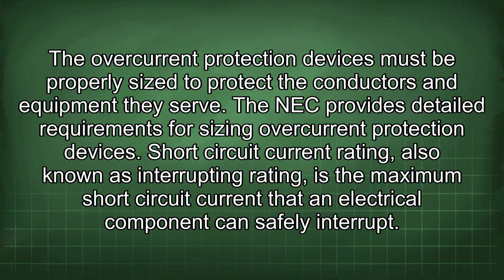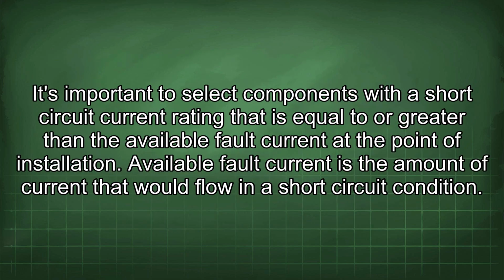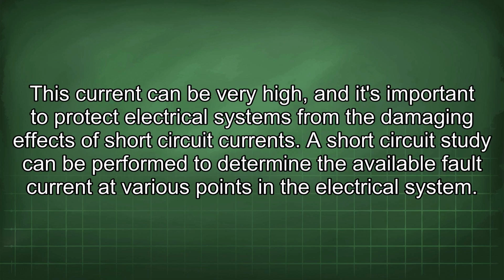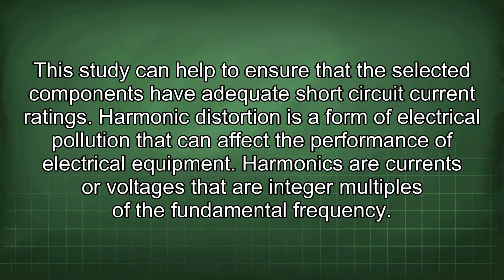Short circuit current rating, also known as interrupting rating, is the maximum short circuit current that an electrical component can safely interrupt. It's important to select components with a short circuit current rating that is equal to or greater than the available fault current at the point of installation. Available fault current is the amount of current that would flow in a short-circuit condition. This current can be very high, and it's important to protect electrical systems from the damaging effects of short-circuit currents. A short-circuit study can be performed to determine the available fault current at various points in the electrical system. This study can help to ensure that the selected components have adequate short-circuit current ratings.